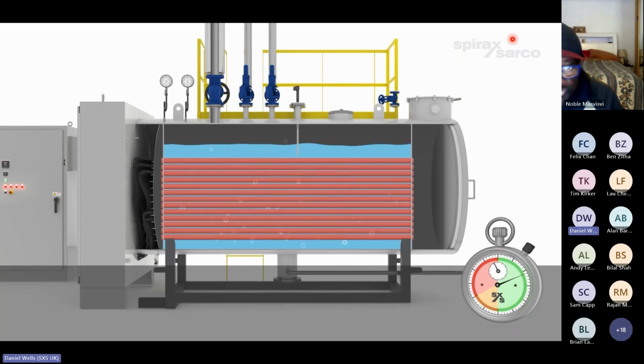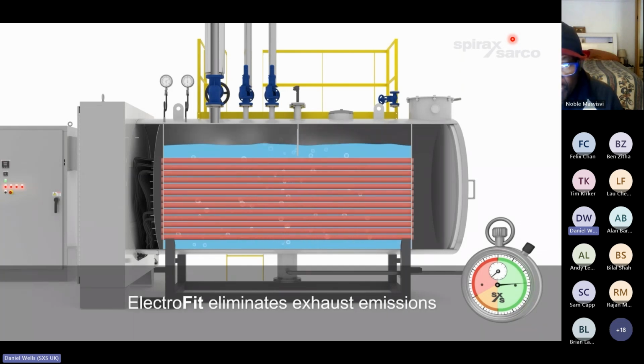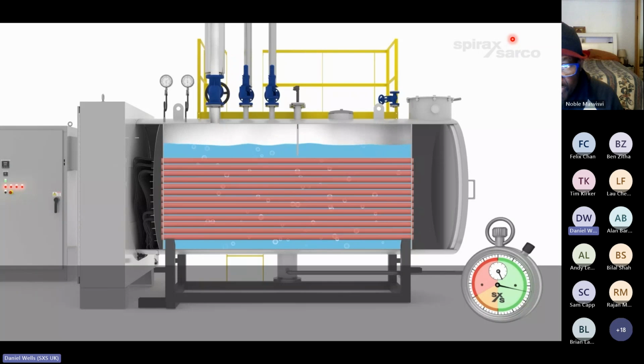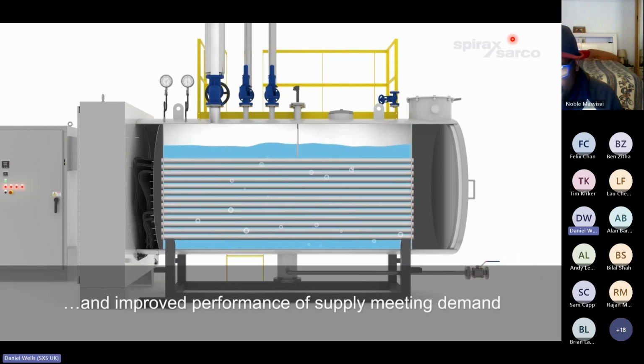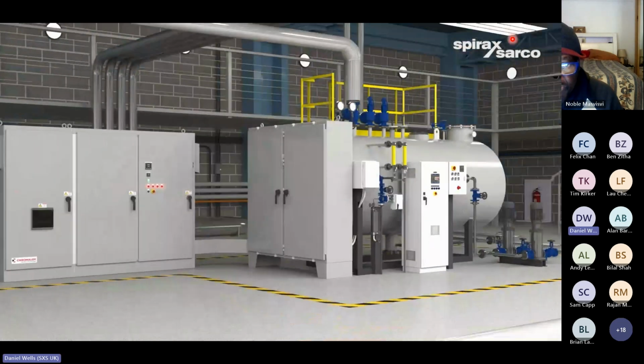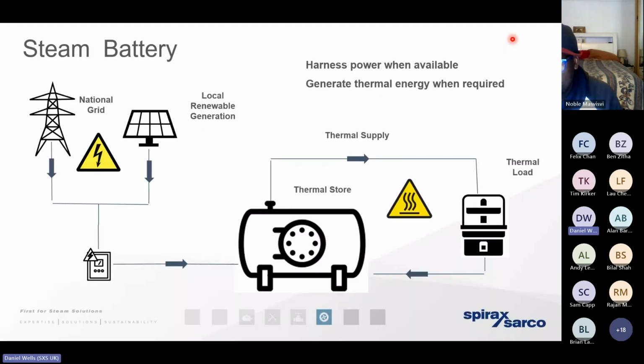We can bring the boiler up to temperature very, very quickly. We've got a very, very even dispersal of temperature throughout the boiler itself. We don't need a purge, and we can get the boiler up to the appropriate pressure and temperature without those carbon emissions that are desperately important that we move away from. So that's what we call an electrofit project. There's another solution that's also very attractive for our client.